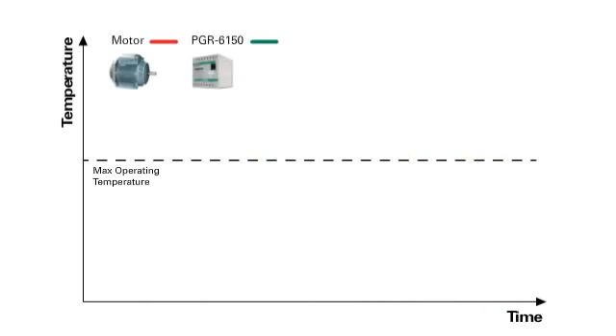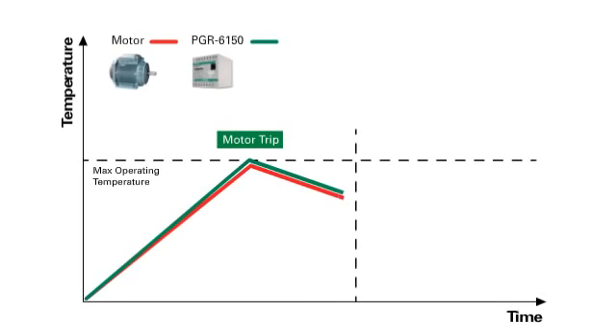The Littelfuse PGR 6150, shown in green, tracks the motor's I²T, thermal capacity, and its temperature sensor output to precisely construct the motor's thermal characteristics. The PGR 6150 can alert of impending problems and will trip accurately to protect motors from damage.